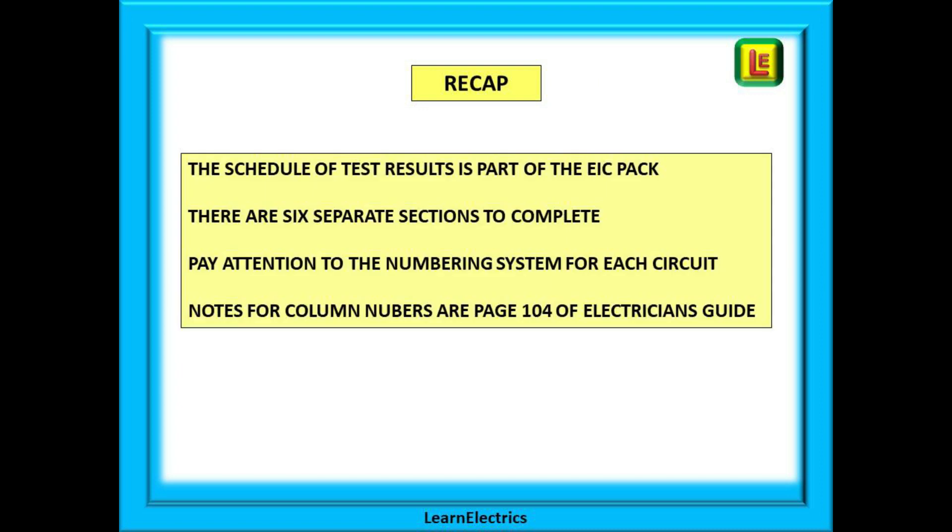A very quick recap. The schedule of test results is not a standalone document. It is part of the pack that is put together with an electrical installation certificate or an electrical installation condition report after a periodic inspection. Look at the schedule as having six separate sections to complete. Completing them one at a time breaks the task down into much easier steps. Good working practice says pay attention to the numbering system. Think about what happens to the numbers if the installation has extra circuits added in the future. And do use page 104 of the electrician's guide to the building regulations. It will help putting information into each column.